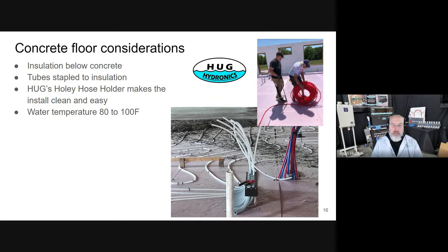Where the ends come up, this is where you want to make sure you keep track of which end is which loop and where it comes up. The loop plans will actually specify a feed and a return side, so that the warmer water coming straight out of the system goes to the right part of the floor where you need just a little more heat, like against the outer wall, for example.